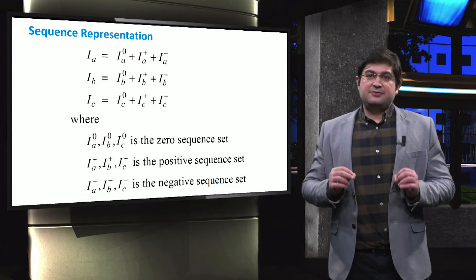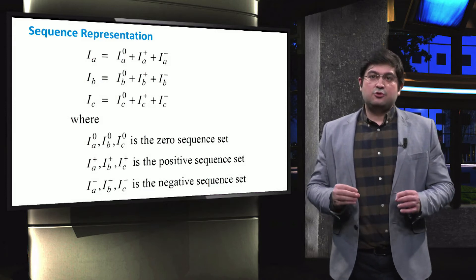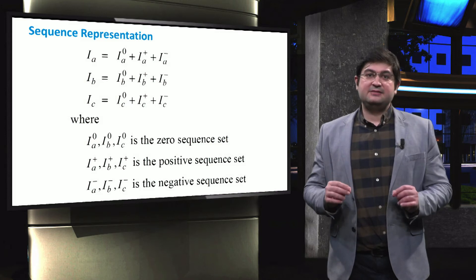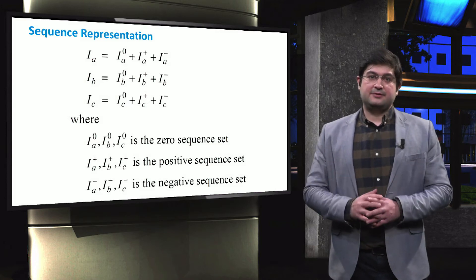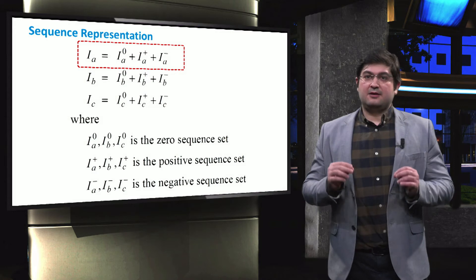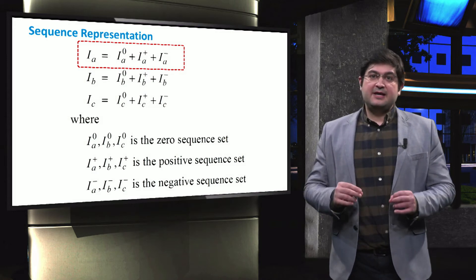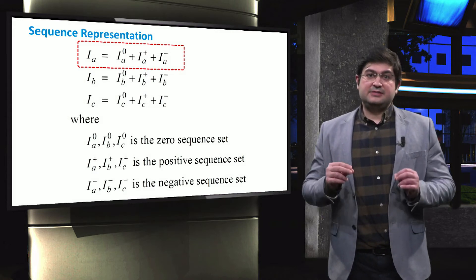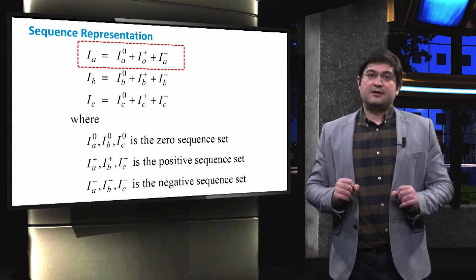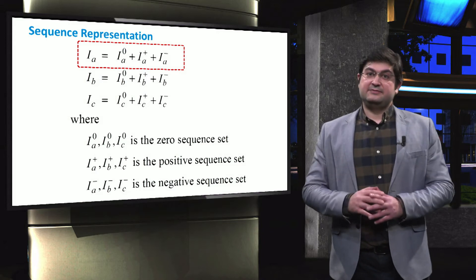If these three sequences are known, then it is possible to obtain the actual three-phase values as shown in the figure. The current of each line, like line A, is obtained by the sum of the current of the zero sequence, the current of the positive sequence, and the current of the negative sequence.